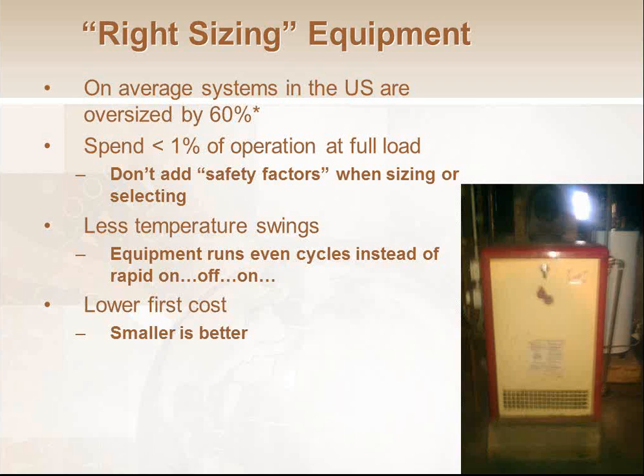Normally people round up. I realize I just said to round down if you're going to round. I'm not saying round down 5 sizes. I'm saying if your load calc comes out to say that you need 305,000 BTUs and your choice is buying a 300 or 400,000 BTU boiler, okay, get the 300. 5,000 BTUs isn't even really measurable. I'm not saying drop down to 100, but don't undersize it. Just correctly size it. That's why we came up with that right-sizing slogan, because we're just tired of people oversizing. But it's a good point, Russell.